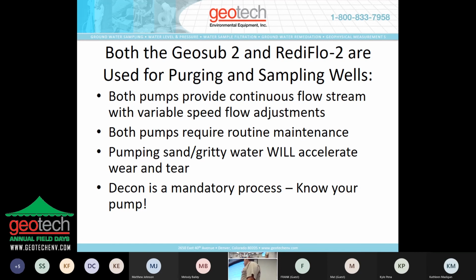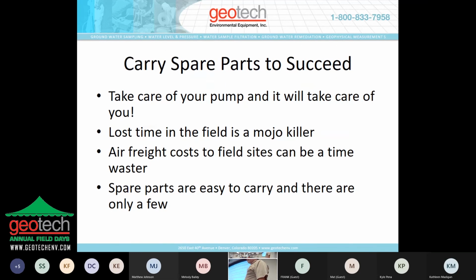Decon is a mandatory process. I always advise people, make sure you know your pump. Carrying spare parts is key to success. If you take care of your pump, it's going to take care of you. There are parts in these pumps that are designed to wear. They're soft parts like Teflon bushings, Teflon wear plates, O-rings, things of that nature that with use will fail at some point. And it's usually when the regulator's on site and it's Friday afternoon and you have to rush off to get samples to the lab and it's the last well. If you've ever had that experience, I have. It's a lot of pressure.